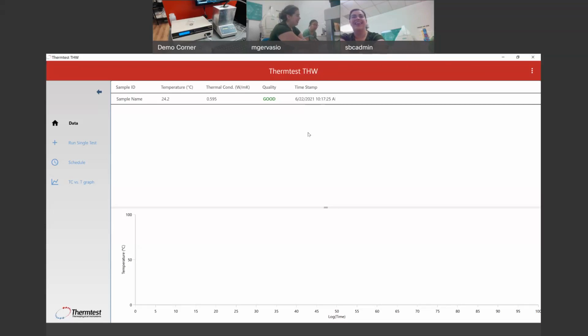A few things you need to check. First, you need to calibrate the sensor with distilled water. Then you can always take the measurements. Also, when it's stable, you can run a schedule with 2, 3 measurements, so you will also see the repeatability.